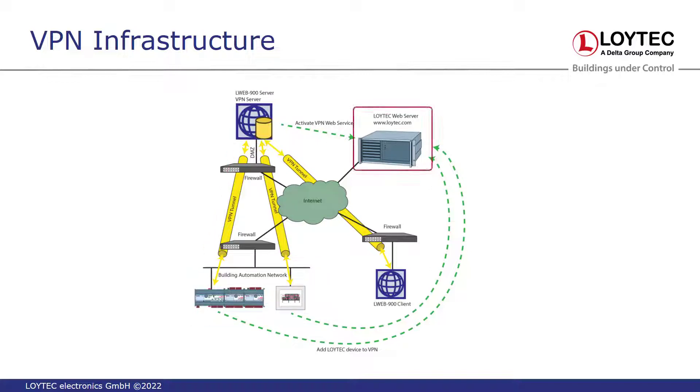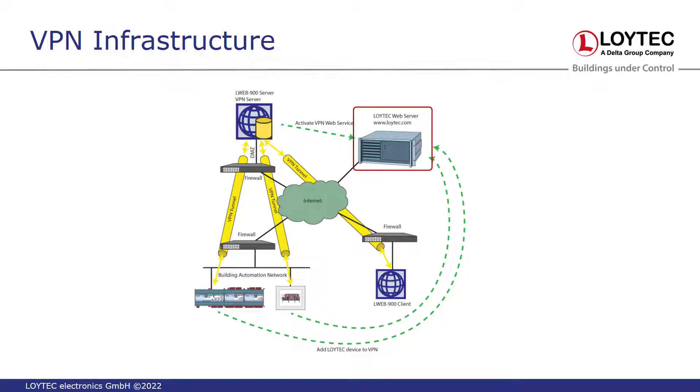LOYTEC devices, as well as the LWEB-900 server, can now communicate with the LOYTEC web server on the internet. The devices will communicate their VPN configuration to the LOYTEC web server, which in turn will automatically configure the LWEB-900 server. And this is exactly what this VPN maintenance license is required for.